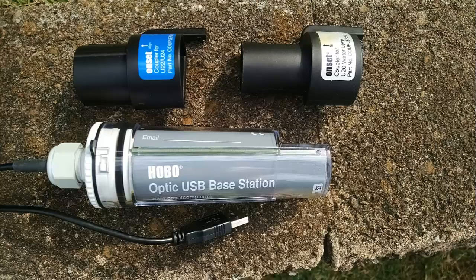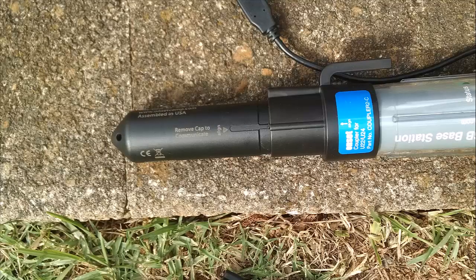And here's the optic USB base station. This is a communication shuttle which allows you to connect one of the water level loggers to a computer for setting up the instrument and reading out the data. Above it are two different adapters for each particular style of water level logger. Once the base station is connected to the USB port of a computer, you will use the HOBOware software to set up and read out the loggers.